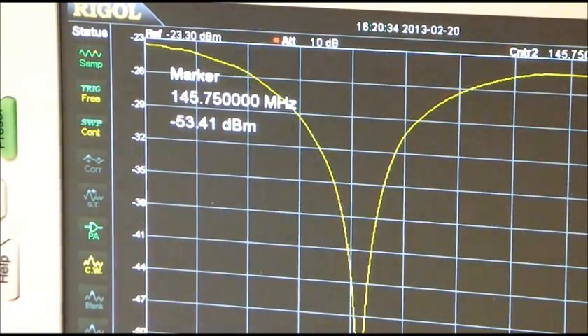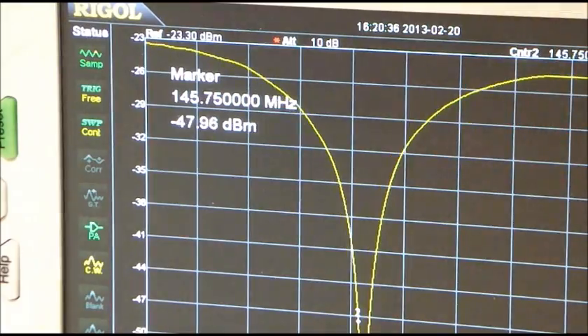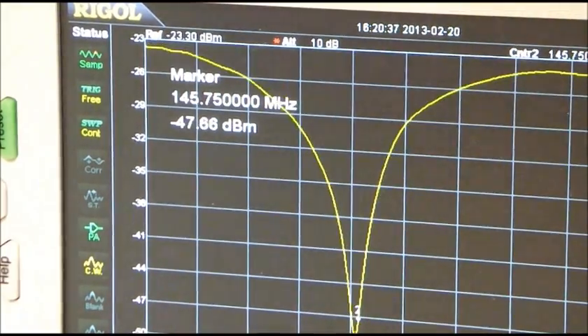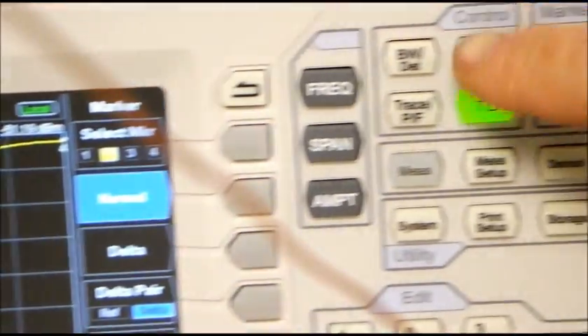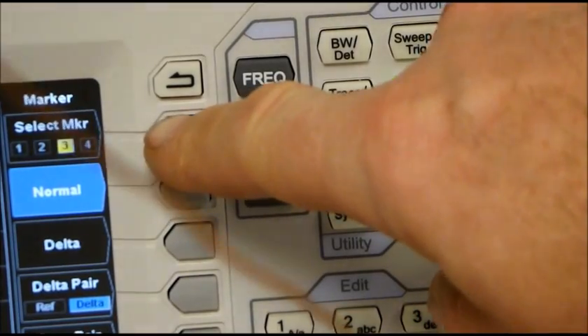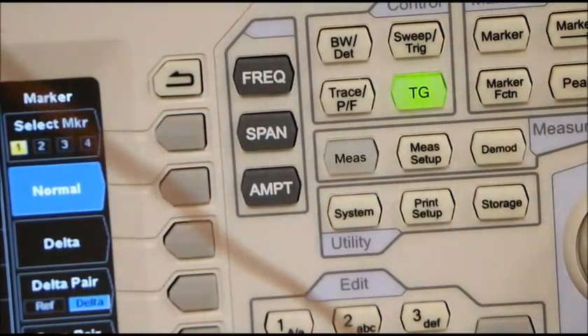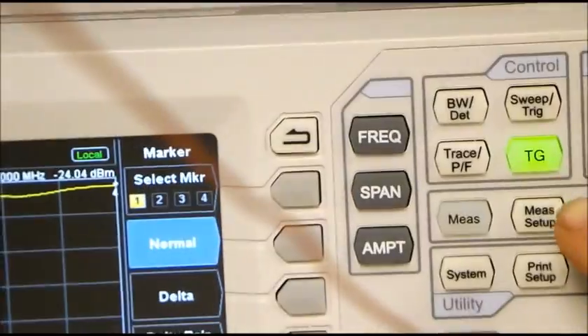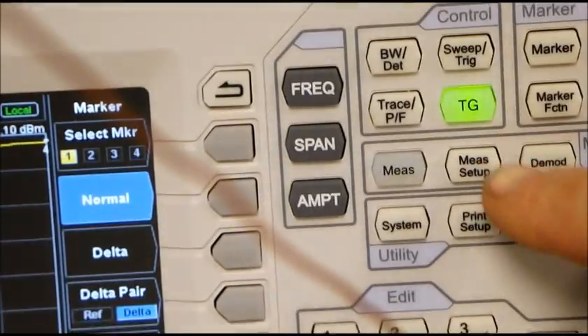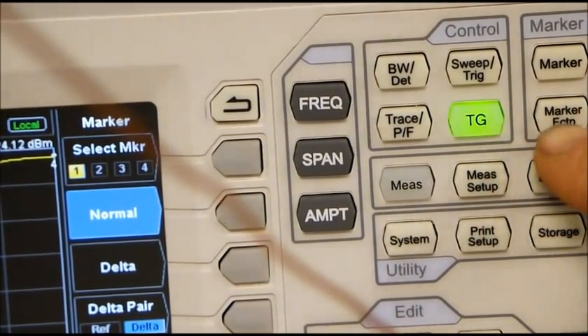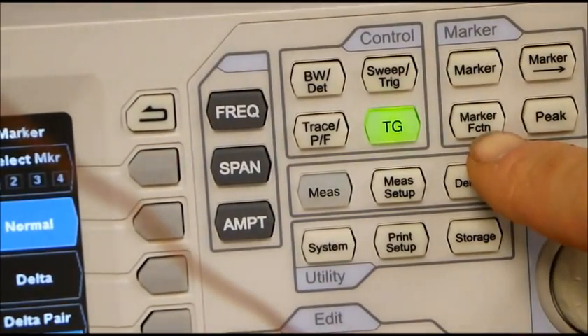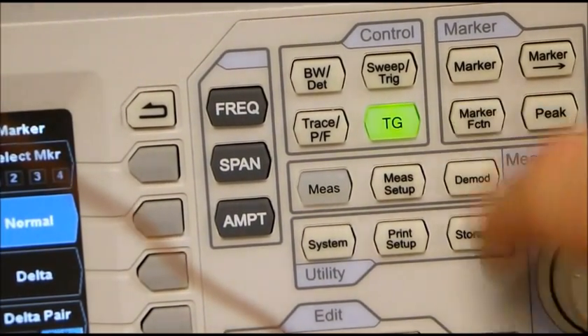The markers' functions in the DSA 815 are extensive. There are many features that you can use. Let's select a different marker. This time we're going to use the marker function button on the analyzer to set a different function. The marker function we're going to use is a 3 dB bandwidth of that trough.